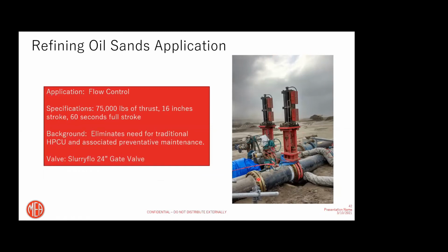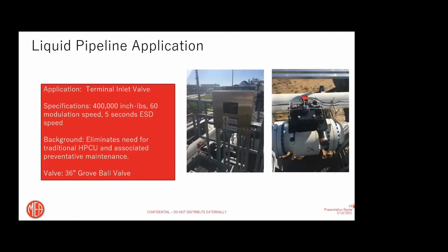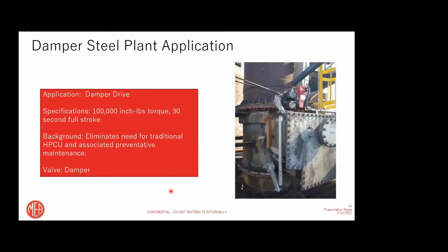And these units have been installed in a super cold environment for a very long time now. And as you can see, it's operational, works great. Additionally, it's a terminal inlet, so there are different sorts of rotary valves you can apply this technology with. This actually sits on a 36-inch Grove ball valve. Additionally, you can put these units on actual damper drives also.